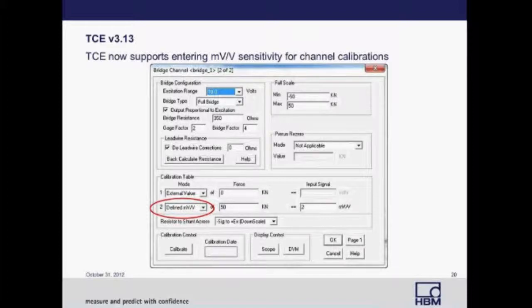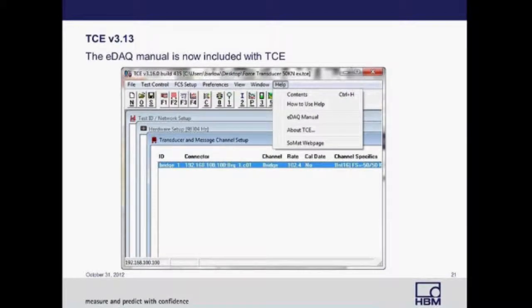In TCE version 3.13, TCE now supports entering millivolt per volt sensitivities for channel calibrations. Prior to this, if you had a transducer with a millivolt per volt sensitivity, you would have to calculate its sensitivity based on its excitation. Now you can define it directly in the pull-down menu on the calibration table. Another update for 3.13 is that the eDAQ manual is now included in TCE — go to the toolbar, select Help, then select the eDAQ manual.